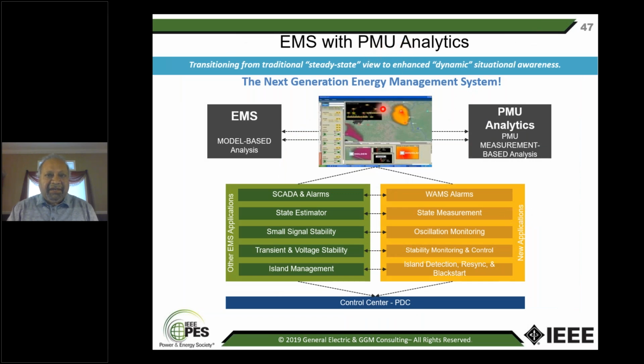So this is what the EMS with PMU analytics looks like. This is the traditional EMS, which uses a network model for your state estimator and all these other functions. And here you have the PMU analytics, which do not need a network model because the grid is your model, getting measurements. And these are analytics which are developed using just digital signal processing and getting data out of this data stream. And so you have wide area monitoring systems, state measurement, oscillation monitoring, etc. And the PDC is the phasor data concentrator, which brings in the PMU data either in here or into the traditional.